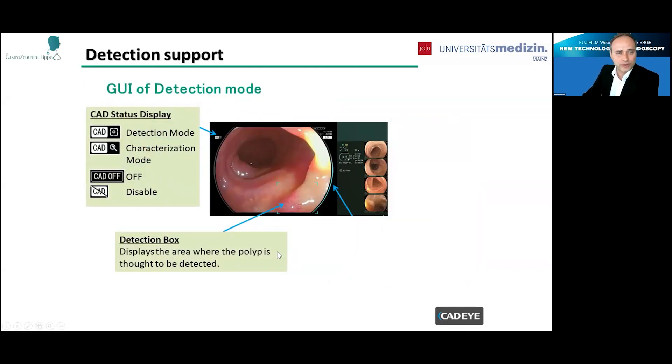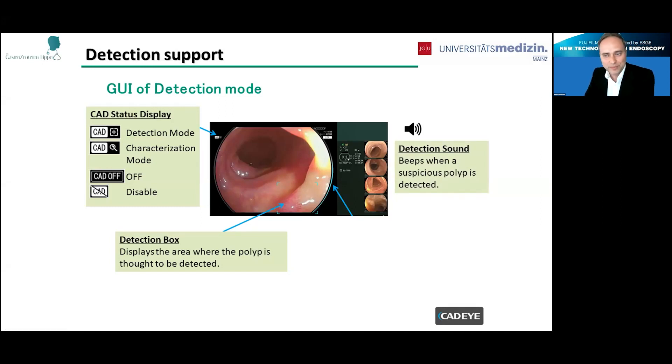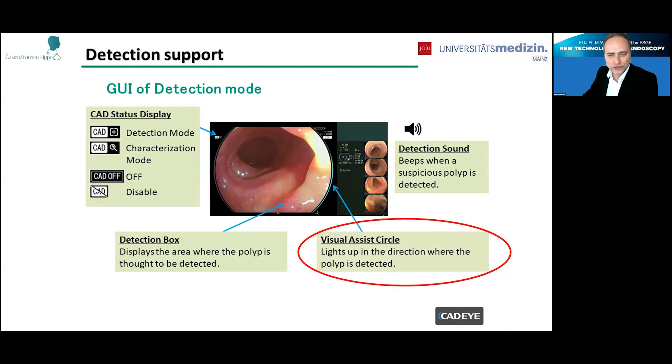The CADEYE is totally different from other competitors' detection systems because we have a specific graphical user interface showing a detection box around where the polyp is thought to be. In addition, we have a specific detection sound — it beeps when a suspicious polyp is detected. We also have a visual assist circle surrounding the endoscopic image, lighting up in the direction where the polyp is detected. For example, if a polyp is detected at the five o'clock position, the visual assist circle highlights that area to help you identify the polyp.